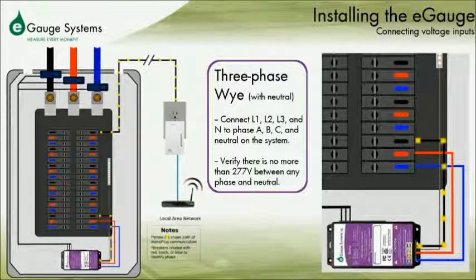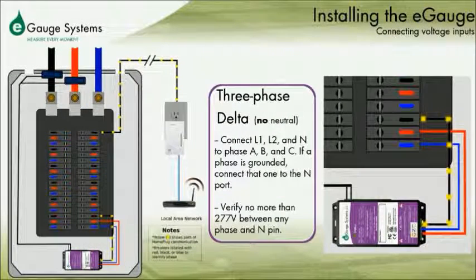Here is an example of a 3-phase system wired into the eGauge. Phase A of the system is wired into L1, Phase B into L2, and Phase C into L3. You will also see the neutral is wired into the N slot. In situations where there is no neutral, one of the 3 phases will need to be wired into the N slot for the eGauge to function.